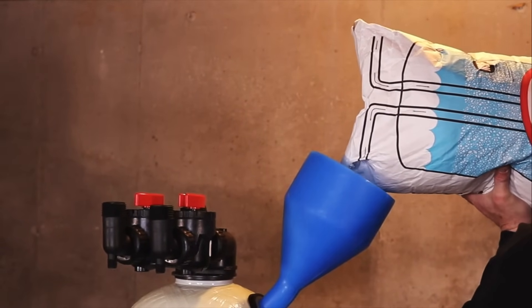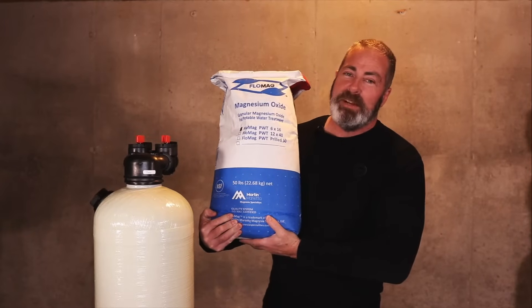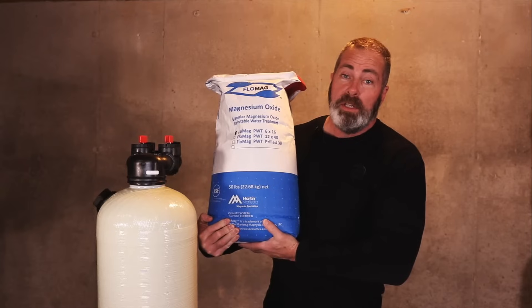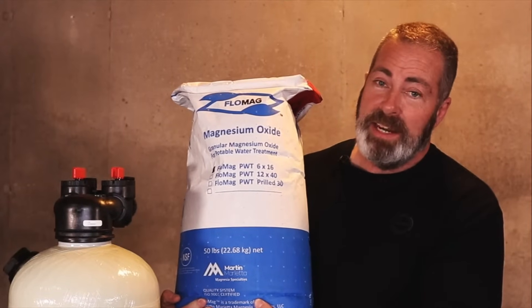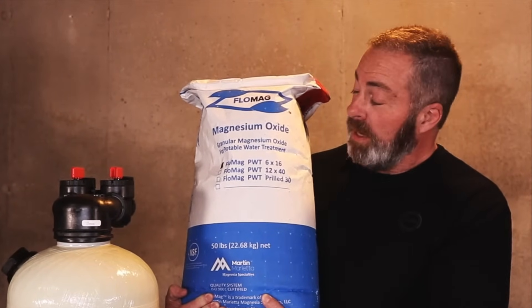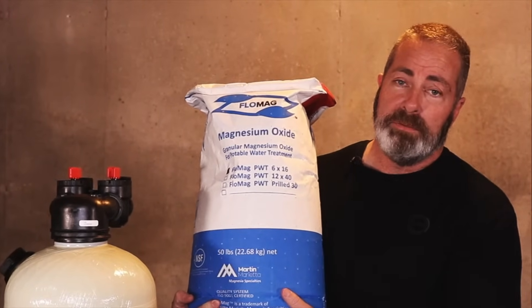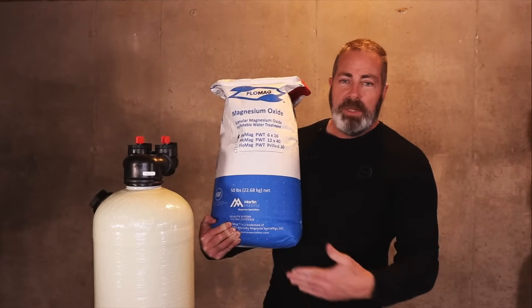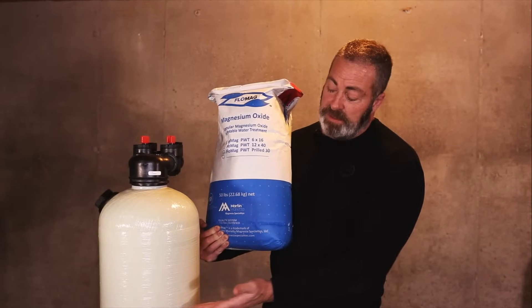You will receive three 50-pound bags of Thomasville Calcite. For pH levels below 5.8, you will need to add FloMag. FloMag is an additive with five times the pH-raising power of regular calcite, and we usually add two or three pounds per 50-pound bag of calcite. We use a storage bin — dump the calcite in first, then add the FloMag, mix it well, and add it to the tank, filling the tank to 10 inches from the top.